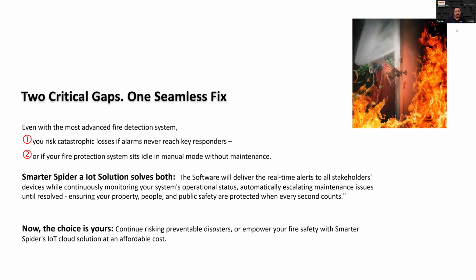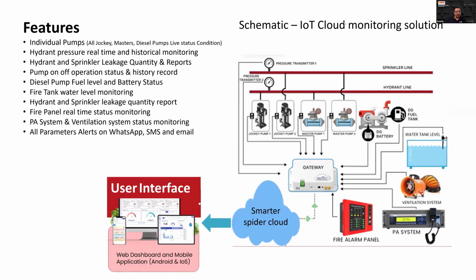I put up a small diagram here, showing how these systems can monitor. You have individual pumps, jockey, master pump, diesel pump, which can be connected through sensors. Hydrant pressure can be checked. Hydrant and sprinkler leakage: if there's a leakage on the pipeline or the sprinkler, that can be reported. Pumps are always supposed to be on auto mode, but at the control panel, because of maintenance, they turn it off and put it on manual, but forget to put it back on auto mode. Those things also can be monitored.